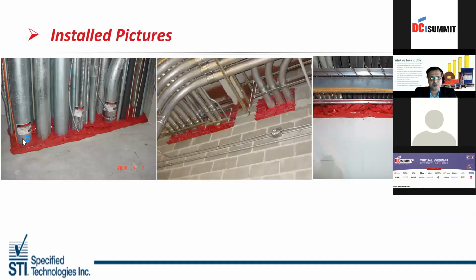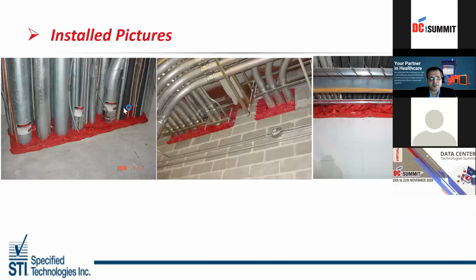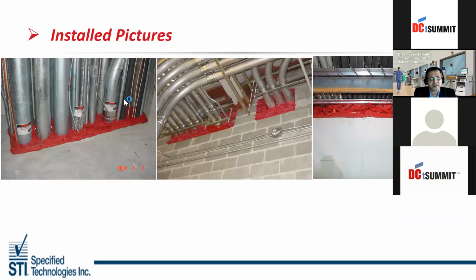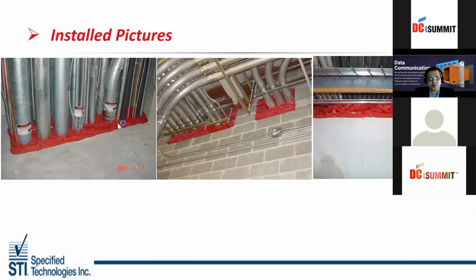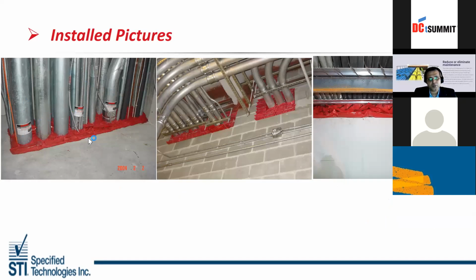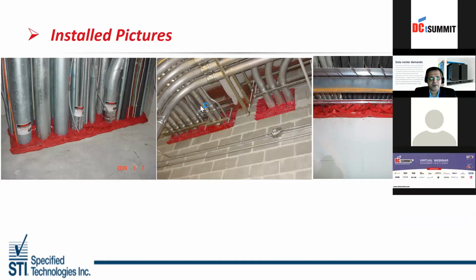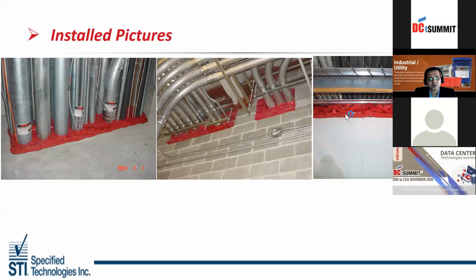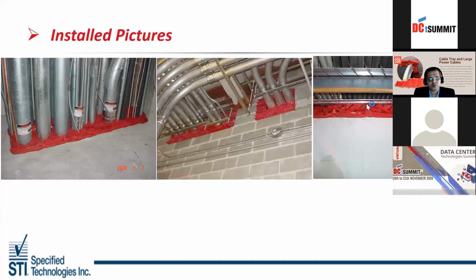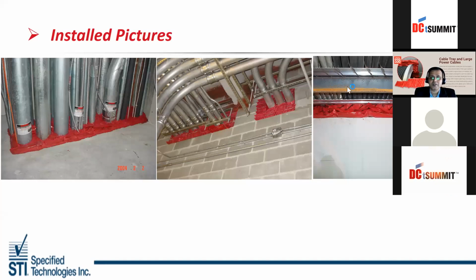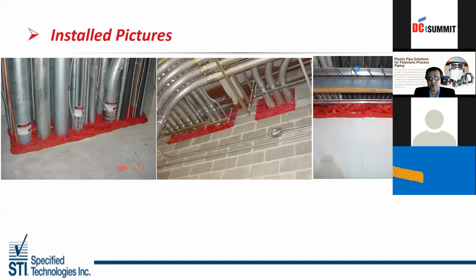Some install pictures: you can see mostly metallic pipes, but here these are the cables. So you have a scenario where you have metallic plus combustible ones. A pillow works better because this is an intumescent product, and it will expand in case of fire. It's a wall penetration, with insulated as well as metallic pipes. Towards your right hand side, you have a cable tray passing through the wall. So a pillow has been installed.